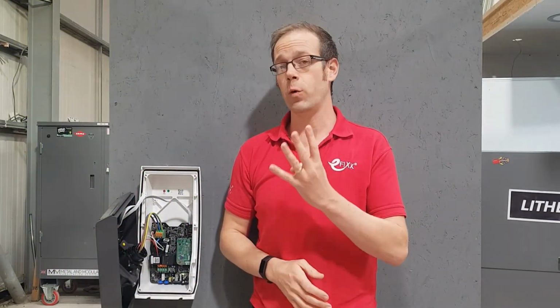The Indra Smart Pro takes advantage of the fact that the reg allows for a period of 4 seconds to pass before the device operates in the event of a PEN fault. Taking advantage of this period allows the device to filter out those brief high voltages that would disconnect chargers from other brands. This also has the advantage that in the event of a proper PEN fault, the charger has a soft shutdown function, which means that it will turn the charger off in a controlled fashion. It's a bit like the difference between shutting your PC down properly versus turning it off at the wall. Shutting down properly allows the computer to protect itself and ensure the continued smooth running of the electronics. The same principle applies to this very clever charger.